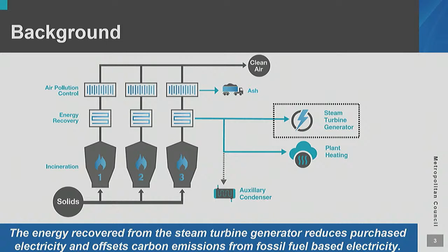Current condition: the G7 steam turbine generator was taken down for 5-year preventive maintenance, and we found problems that needed to be addressed before the unit could be put back into service. The inspection found internal corrosion and erosion and a bowed rotor shaft. Refurbishing the existing rotor would cost more and have a longer lead time than ordering a new rotor. The recommended rehabilitation consists of repairing the turbine case, the extraction case, the diaphragms, and replacing the rotor assembly.